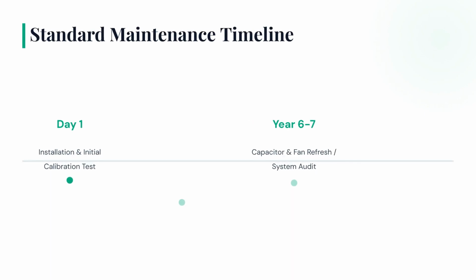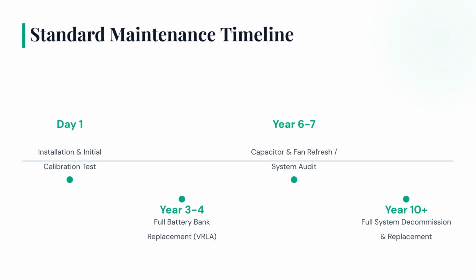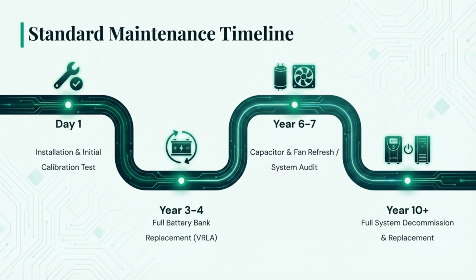A standard maintenance timeline starts with installation and calibration. Plan for VRLA battery replacement around years 3 to 4, a system audit and capacitor/fan refresh around years 6 to 7, and full system replacement by year 10. Adhering to this timeline minimizes the risk of component failure and downtime, maintaining optimal protection.